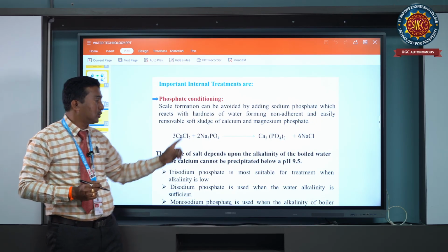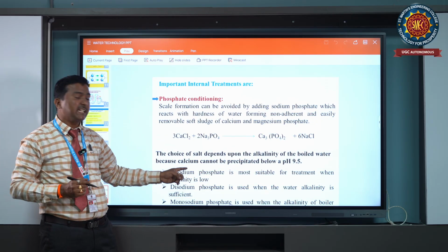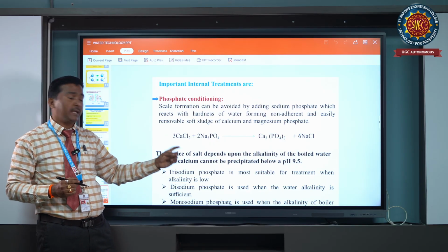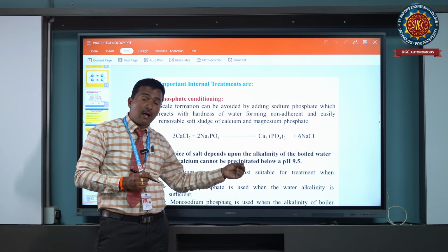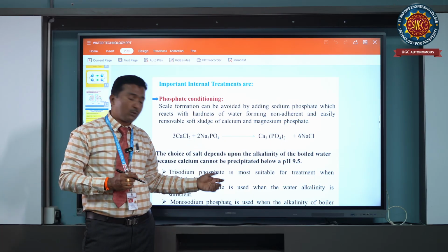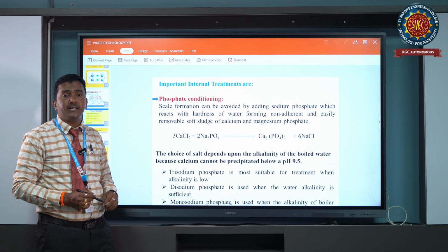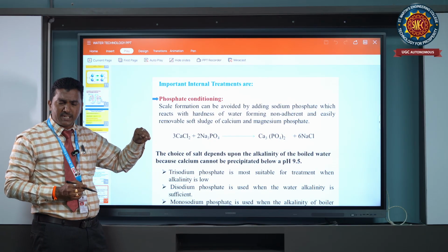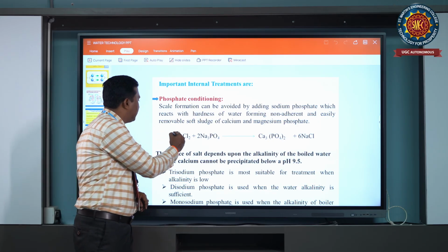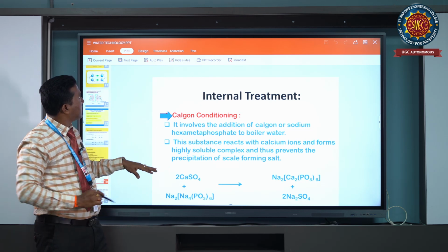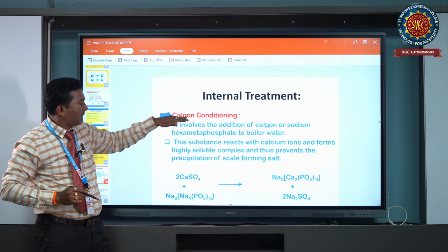Trisodium phosphate is used when the alkalinity is very low. Disodium phosphate is used when the alkalinity is sufficient. Monosodium phosphate is used when the alkalinity is high. Based on the nature of the water, we add these chemicals.